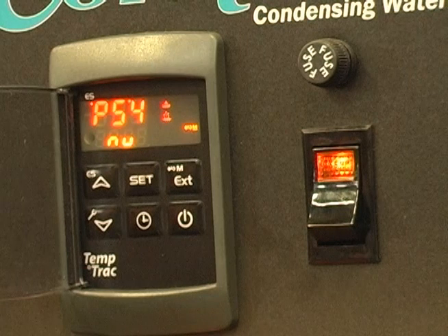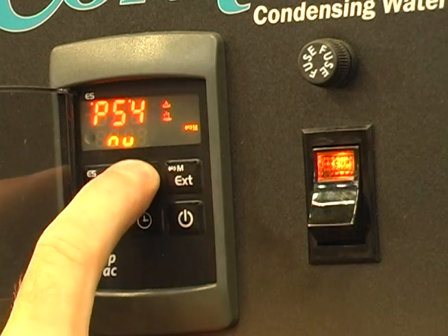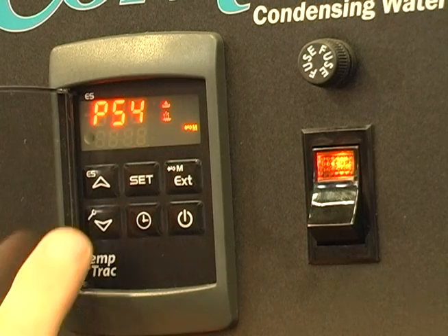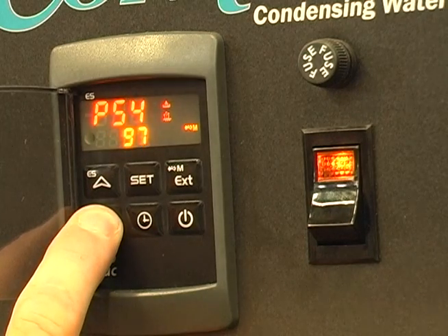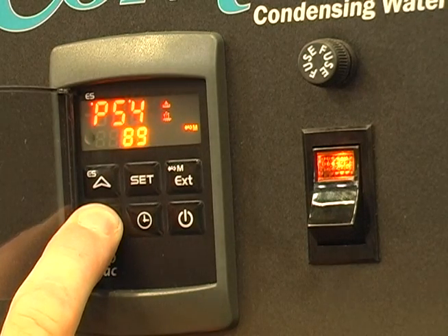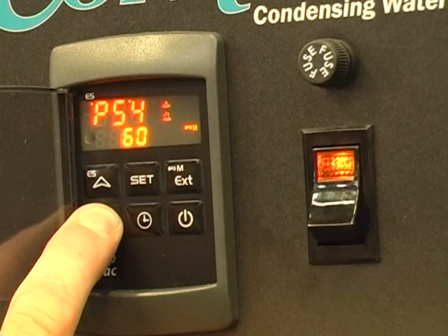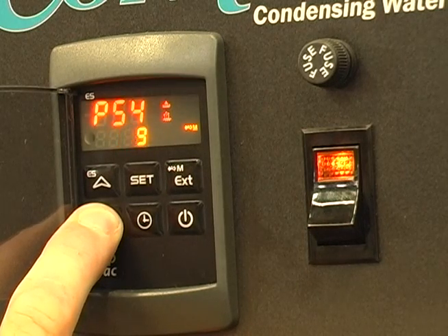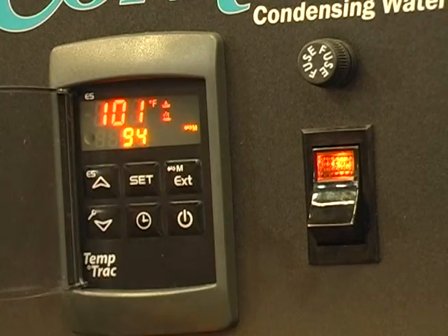Now that the password is set, the value for P54 parameter will appear in the lower display. This parameter should read the factory default of NU, or not used, which means the water heater is set to operate in automatic modulation mode. To manually adjust modulation to low fire, push the set key. When the value starts flashing, press the down arrow key until the parameter reads 0 for low fire. Press the set key once more to lock the control into low fire.